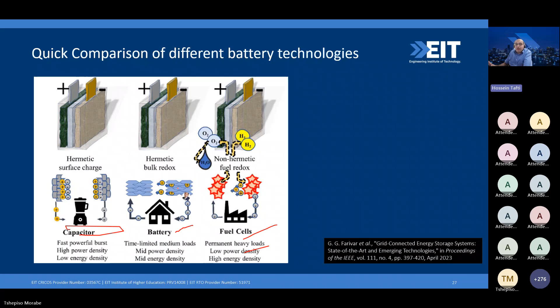An overview of different types of batteries and their comparison of energy and power density is shown here. Lead acid batteries have relatively low energy density as well as low power density, which is why they are not normally used for energy storage systems or grid applications. They are used a lot nowadays for uninterruptible power supplies. The big difference between UPS and energy storage systems is the number of times the battery needs to be charged and discharged. In lead acid batteries used for UPS, the battery normally remains at full charge or idle, and doesn't need many cycles of charge or discharge. On the other side, energy storage systems require many cycles of charging and discharging.